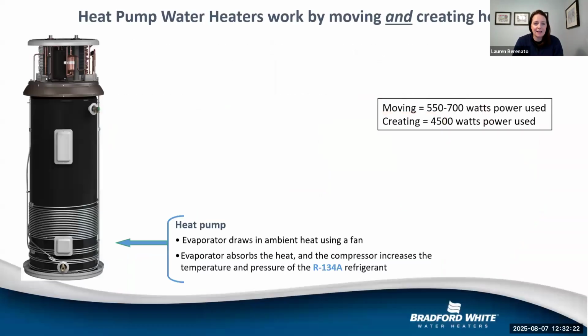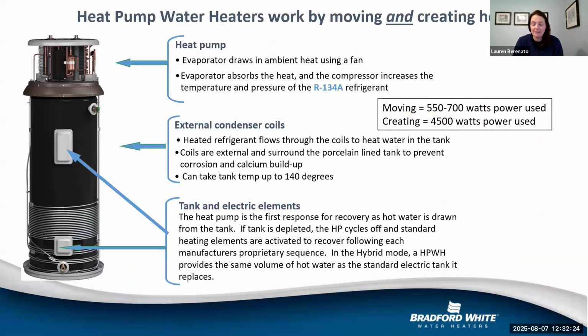Now, this next slide I think is really great because it shows you the internals of a heat pump once you take the jacket off, what it looks like underneath. So you can see right there on the top of the system, and again, this is a single unit. The heat pump is at the top, and it identifies where your evaporator draws in ambient heat using a fan. Your evaporator will absorb the heat, and the compressor increases the temperature and pressure of the R134A refrigerant.